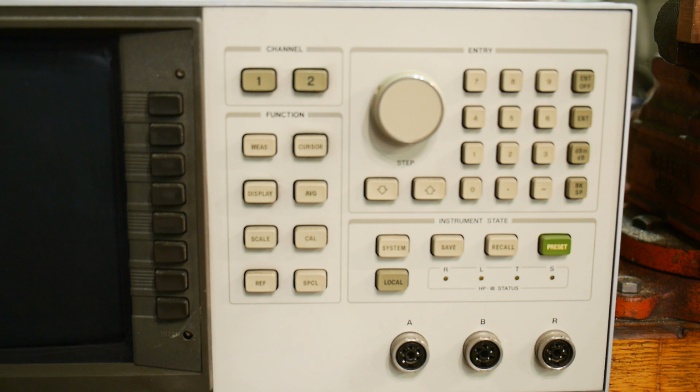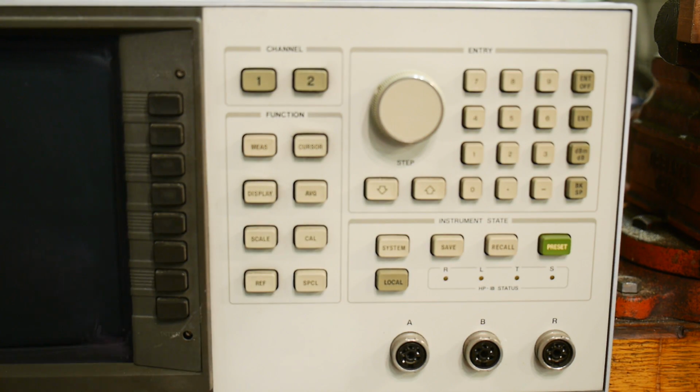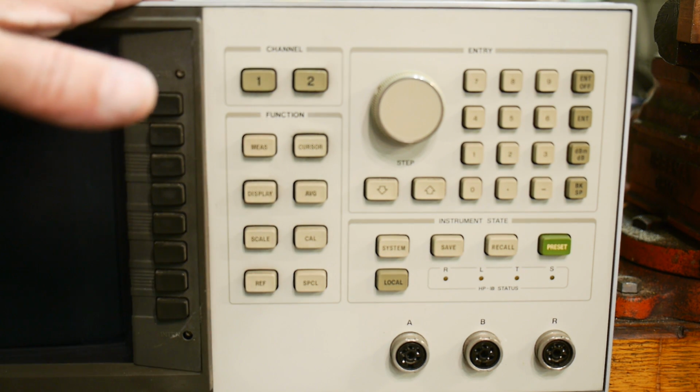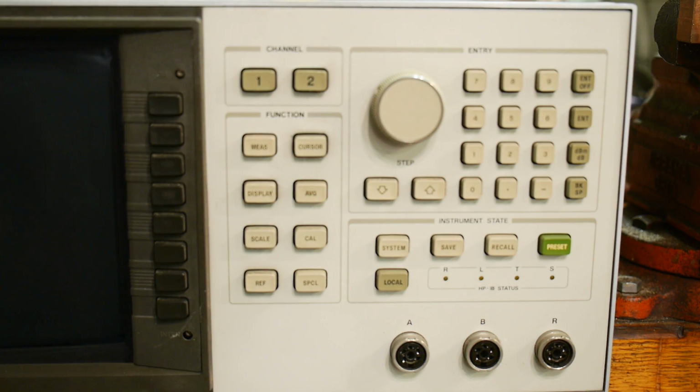Plus you need couplers, plus you need a tracking generator. So this does not have any source output, so you need a tracking generator. Now, these are set up so that they automatically talk to the tracking generator. So when you push the buttons on this, it automatically changes the settings of the tracking generator. But that's, so you bought one of these for $20,000, you bought a tracking generator for $20,000, you spent another $15,000 on sensors. This is a really expensive piece of kit. But what you get is something that's super, super accurate, okay? It's really accurate. So let's take a peek inside.